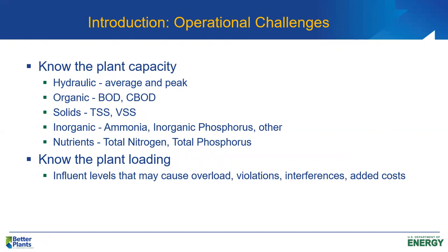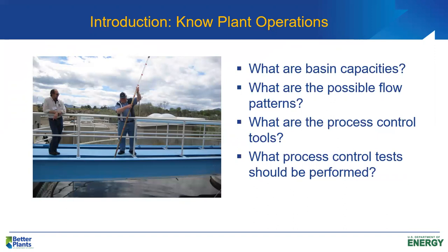We have to know those mass loadings because they show us where we are compared to our design loadings — are we underloaded or at capacity? Are we overcapacity? Are we in danger of violating our permit? Do we have a problem with interferences, or are we spending too much money operating the plant because of loading conditions? We also have to know our plant operations: basin capacities, the volume of each tank, how we can direct flow through the treatment plant, how we can return sludge and return side streams from sludge processing, and what our process control tools are.